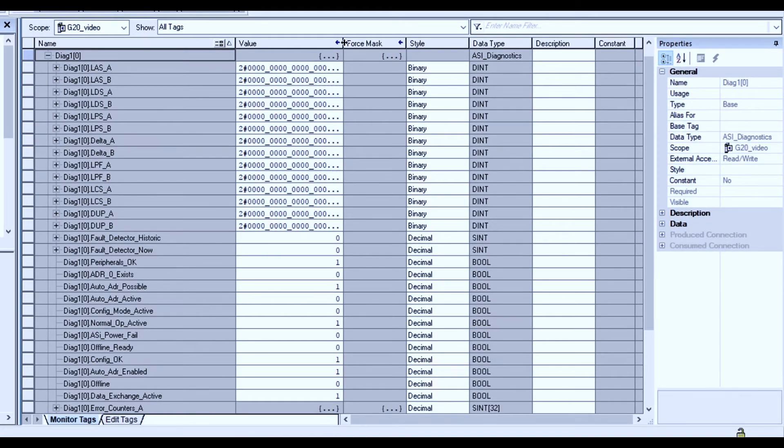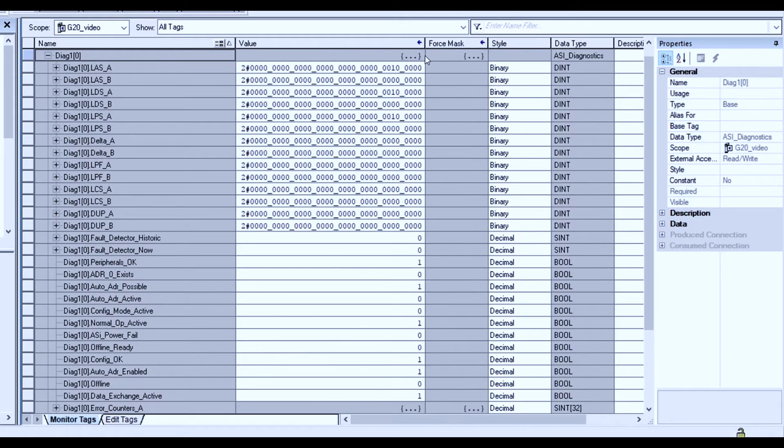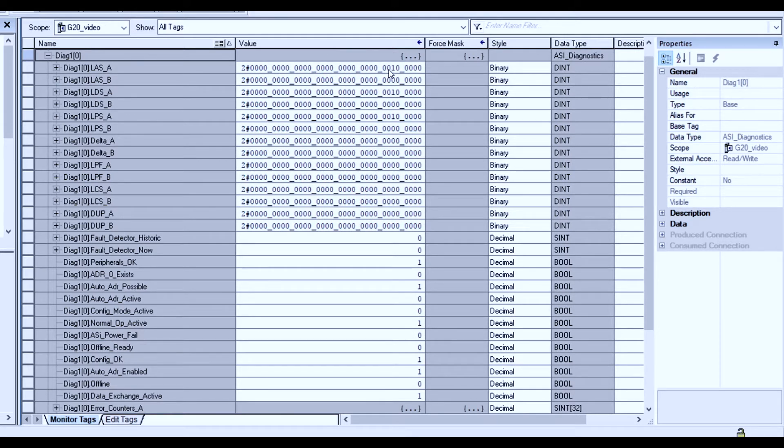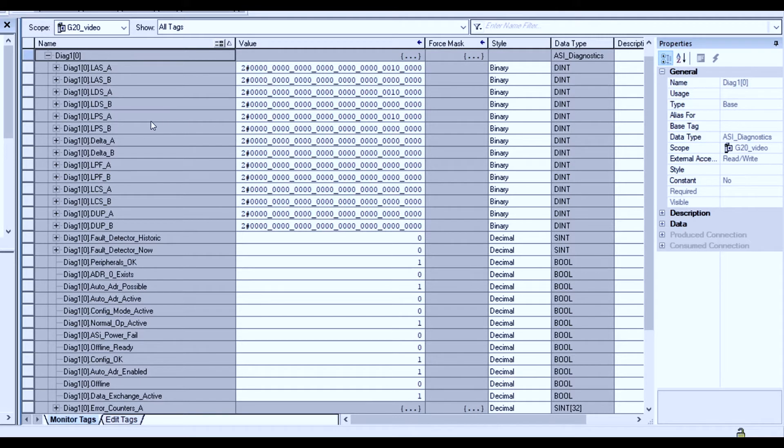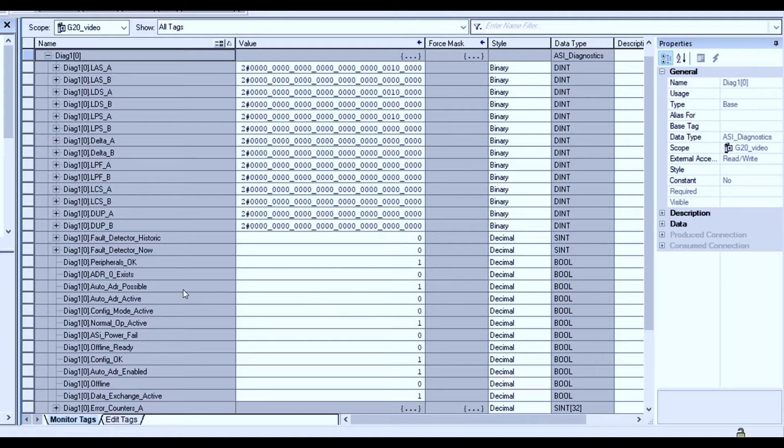We observe a set of diagnostics. First, the list of activated slaves corresponding with the only node address being node 5 on our network. The list of detected slaves, list of projected slaves, and so forth. But furthermore, it has a number of other diagnostics noted. Peripherals being okay in our case, auto addressing possible, etc.